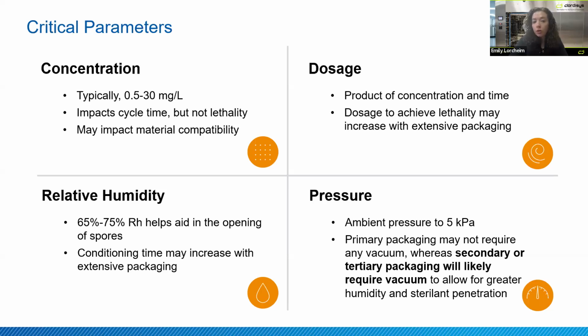For pressure, we can do from ambient, and typically we'll pull down in our deepest vacuum to 5 kPa, just to explain why you may need to fluctuate your pressure. So if you have a simple device, no extensive lumens or tiny crevices in your device, you can have just ambient pressure. So almost think about, say, a Band-Aid in a Tyvek pouch. That could handle just ambient pressure. Now, if you do have secondary packaging or tertiary packaging or a lot of complex design in your device, that's when you would introduce vacuum. So most medical devices and pharmaceutical products do require pressure. Now, you can also adjust that pressure level to be more suitable for your device.